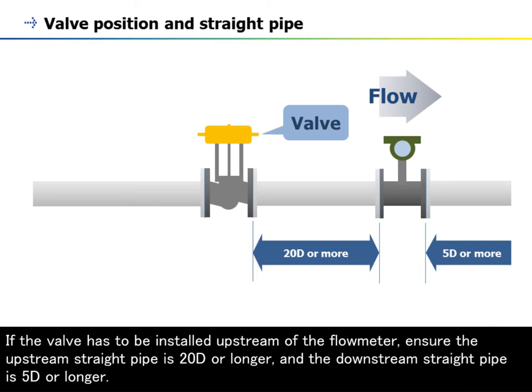If the valve has to be installed upstream of the flow meter, ensure the upstream straight pipe is 20D or longer, and the downstream straight pipe is 5D or longer.